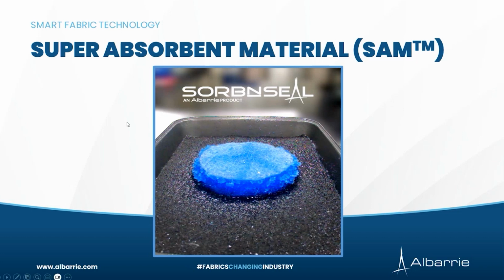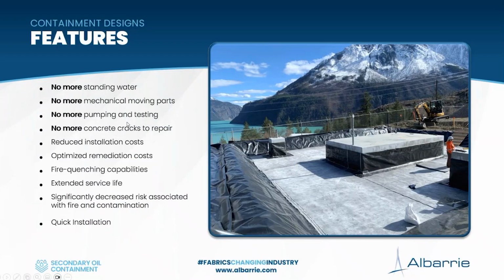This becomes very useful when designing a containment system. The entire floor area of the containment system is this mat that separates oil and water, and it's permeable to water. The area around the perimeter, as well as all the concrete structures, is an impermeable liner that funnels all the liquid towards the floor of the containment, which is this mat that separates oil and water.